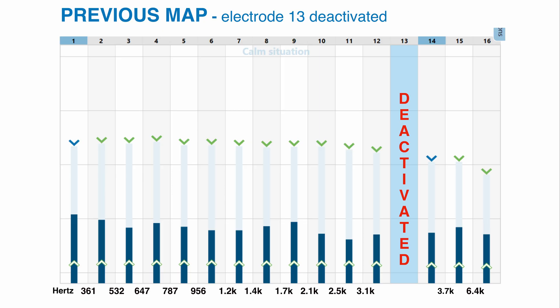This is the map I walked in with that morning. Electrode 13 is turned off and nothing is set to span mode. I'd brought my Bluetooth speaker and some test material preloaded on my phone. One great piece of testing material I've been using was the opening lines of the Beatles classic, Hey Jude. The opening line is: Hey Jude, don't make it bad. Take a sad song and make it better. Now that I've got that earworm stuck in your head, imagine that Paul had taken a big hit of helium before he started to sing — that's what it sounded like in my left ear with all electrodes active. But with electrode 13 turned off, it sounded like my left and right ear both agreed he was singing at fundamentally the same pitch. No more helium. It was a big improvement, and I lived with that setting for about a month.